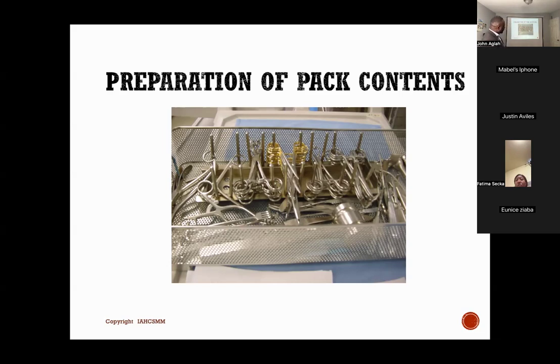All the ring handle instruments are in there. Have you seen that? And they are open right here. Then it still allows for the ring handle instrument to be open. The tip of the instruments are open. That is important because that's what regulatory organizations require. Not just that, that is what the instrumentation manufacturer's instruction states. That is why the regulatory bodies make sure that we are following what the manufacturer's instructions say.